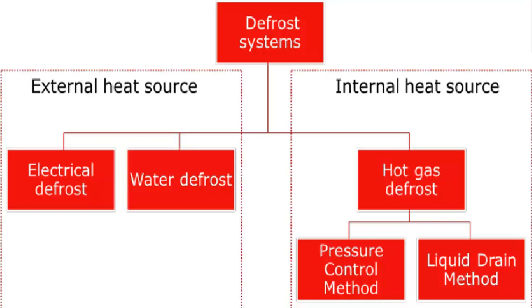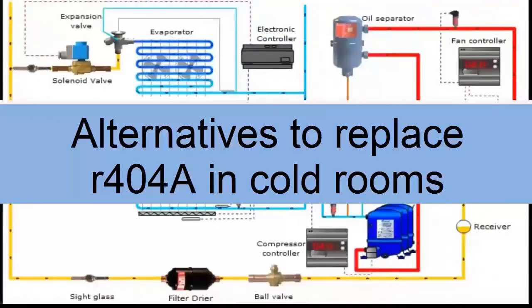Depending on the application, with the use of electronic evaporator control you can choose between the following defrost methods: natural, where the fans remain active during defrost; electric, where the heating element is activated; or hot gas, where the solenoid valves are controlled so that the hot gas can pass through the evaporator at this moment.